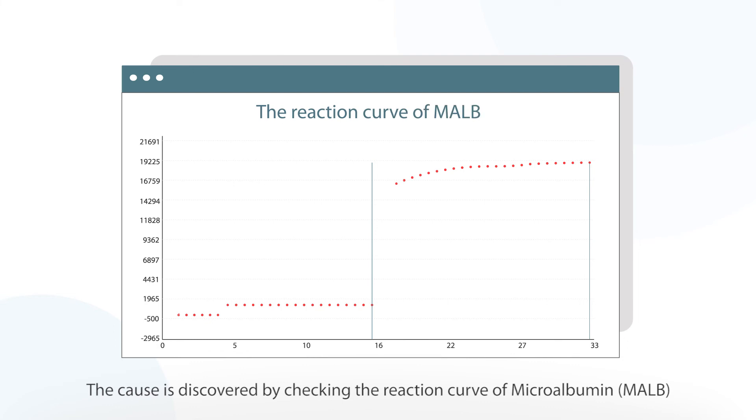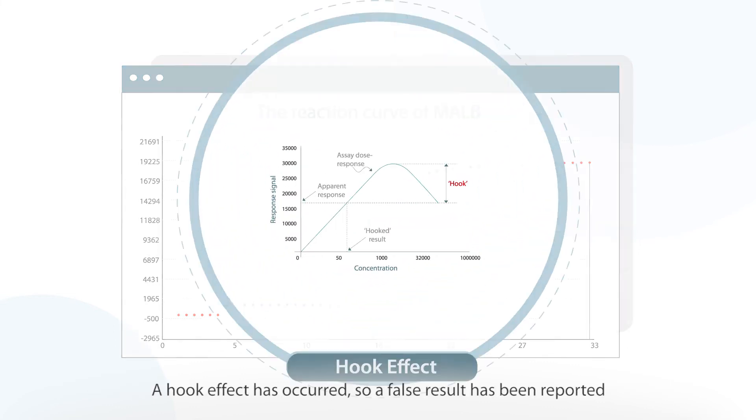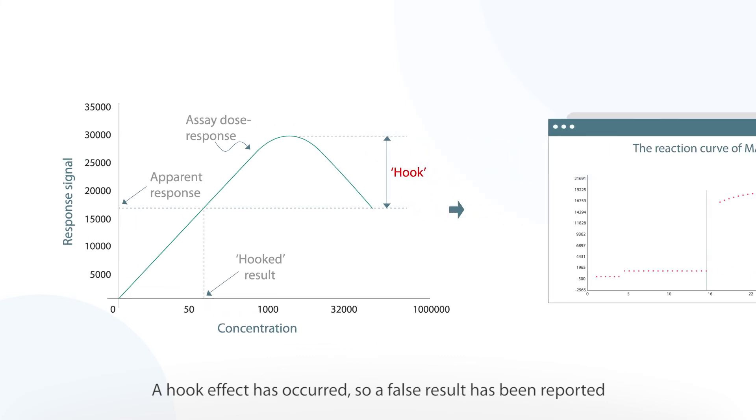The cause is discovered by checking the reaction curve of microalbumin. A Hook effect has occurred, so a false result has been reported.